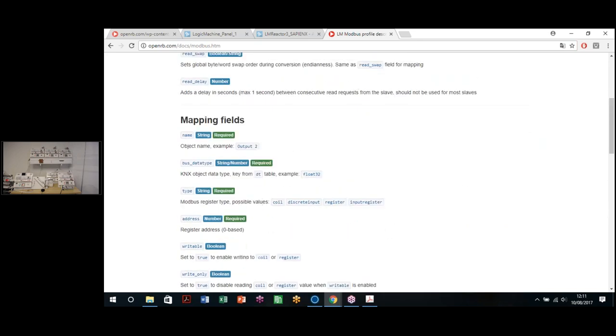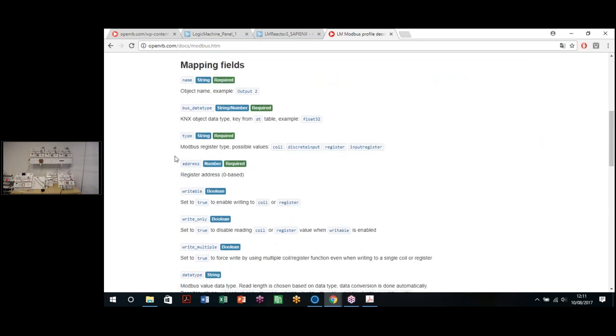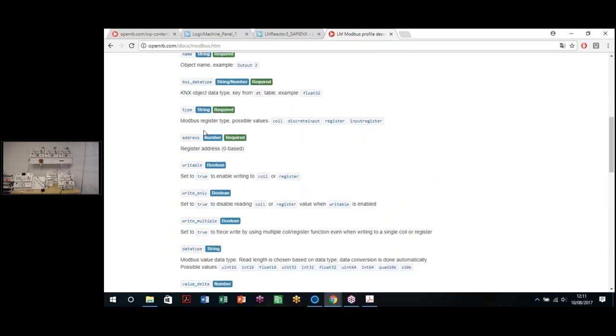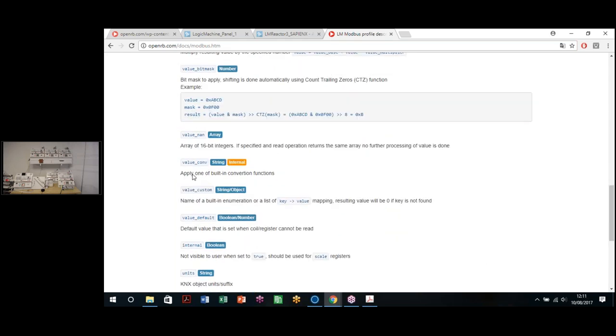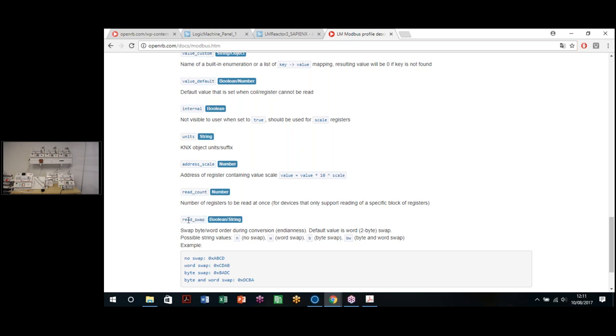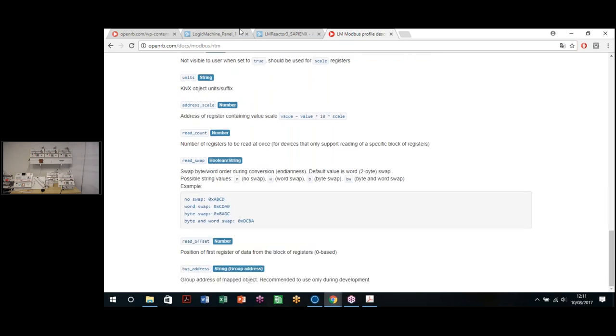We can also set different, not only a bus data type, but we can also set a specific KNX address to that object. So when we insert it into the LogicMachine, it's a little simpler. Of course, this is recommended only during development, but we can also set it. And we can also change information such as byte swaps. This all will depend on the manual of our device.